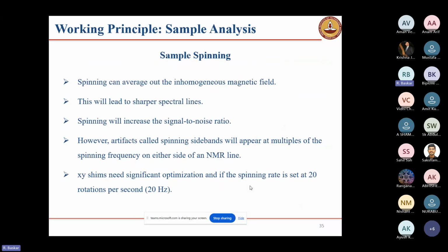Next, I am moving on to the working principle. Once we have prepared the sample, we put it in the spinner and keep it in the instrument. With the airflow, it will reach the probe. Once it reaches the probe, the very first step is sample spinning, a mechanical spinning. The spinning will average out the magnetic field inhomogeneity. This leads to sharper NMR spectral lines. Spinning will increase the signal to noise ratio.